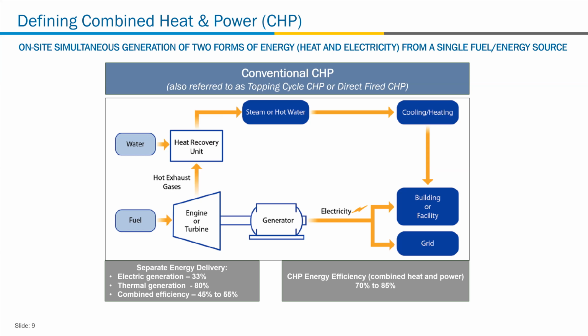This is referred to as a topping cycle, or conventional cycle. You basically have a prime mover, which could be an engine or a turbine of some sort, driving an electric generator to create electricity. Then you have the waste heat from that going to a waste heat recovery unit, creating some form of thermal energy, either hot water or steam, that can also be converted into chilled water. So you can provide thermal energy to a building.